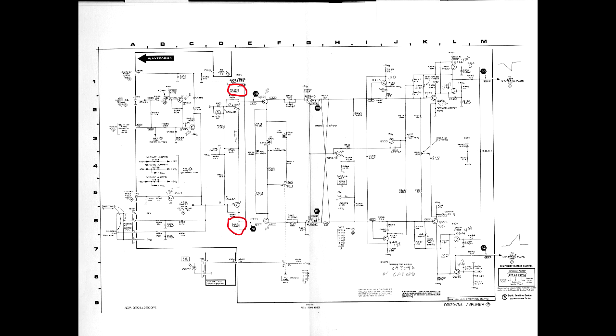I had a 468 with the beam stuck in the center with no deflection. Both horizontal deflection plates were at plus 105 volts. A 465B had the beam off screen to the left and could be brought on screen with the beam finder button.